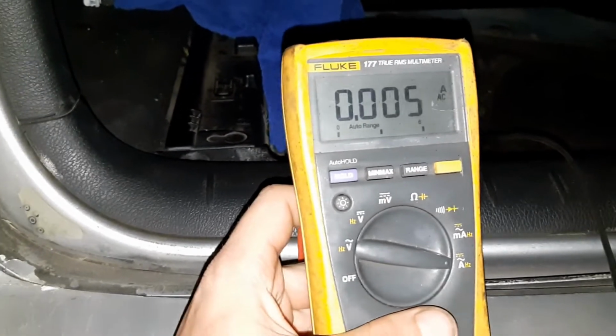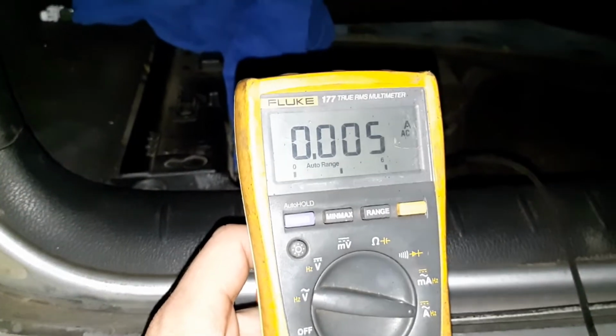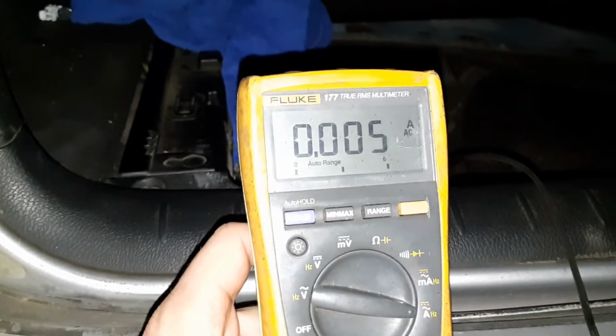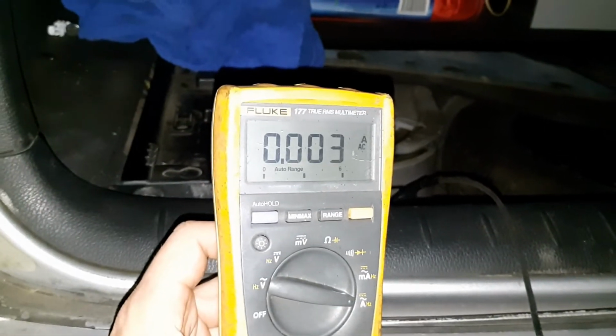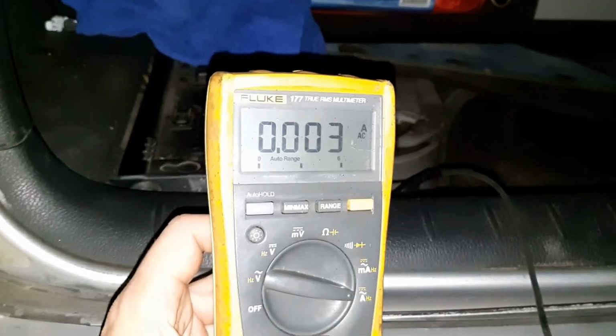Now when you put the alarm on and lock the door, okay, let's lock it, stuff can change. So lock the doors and we'll leave it like that for 15 minutes, because there are computers, they may consume stuff. So we're going to look for anything above 50.